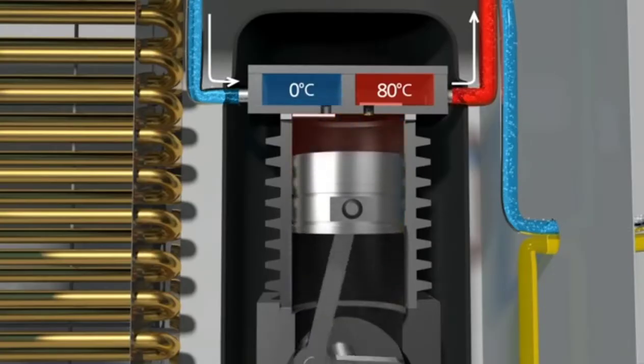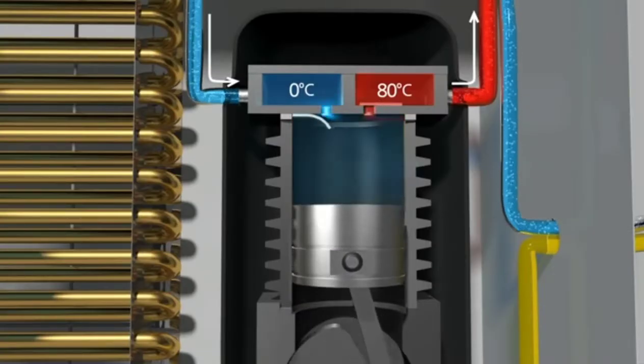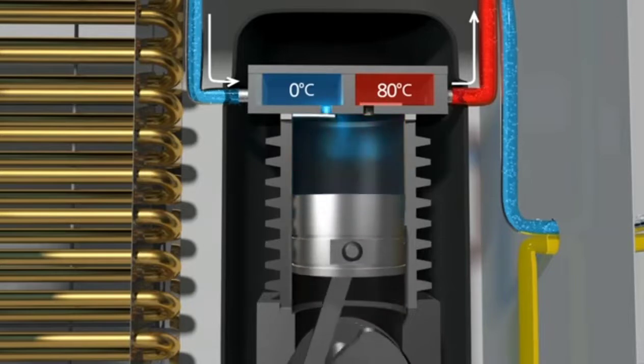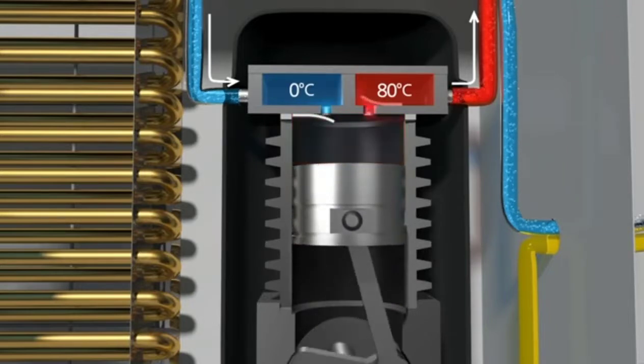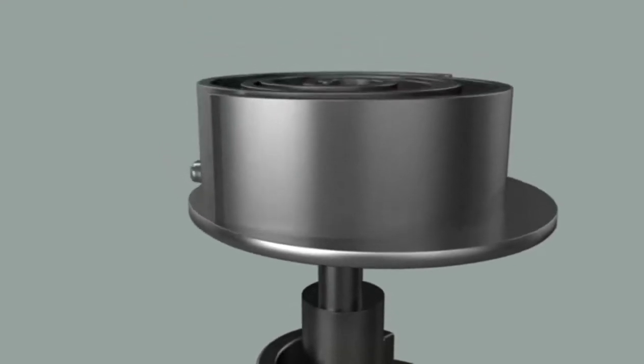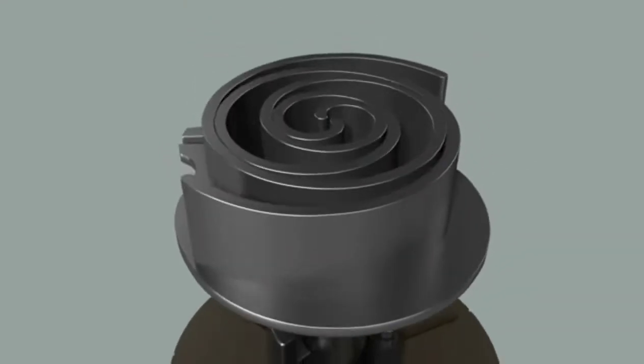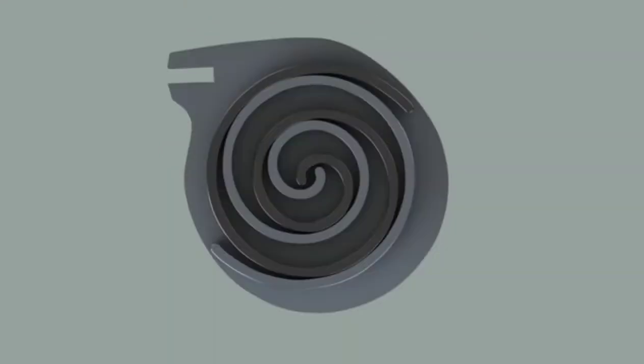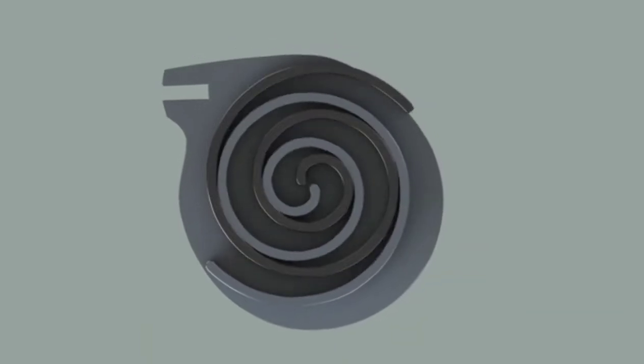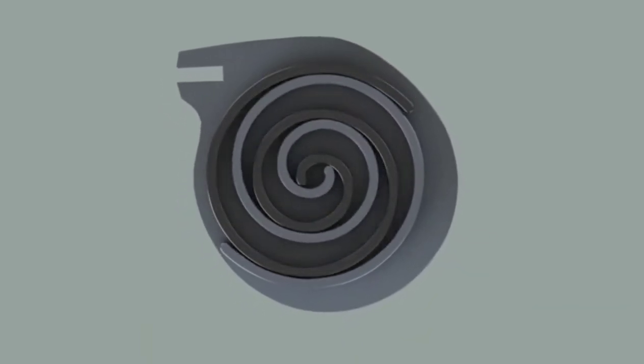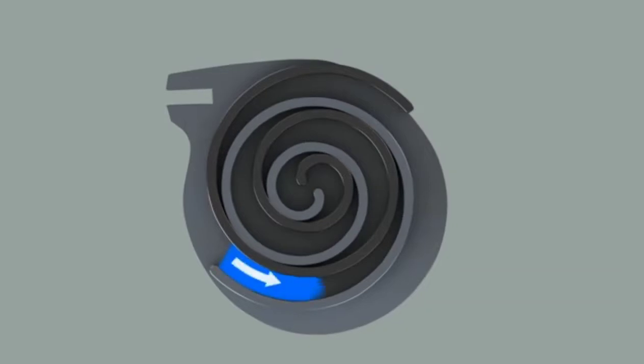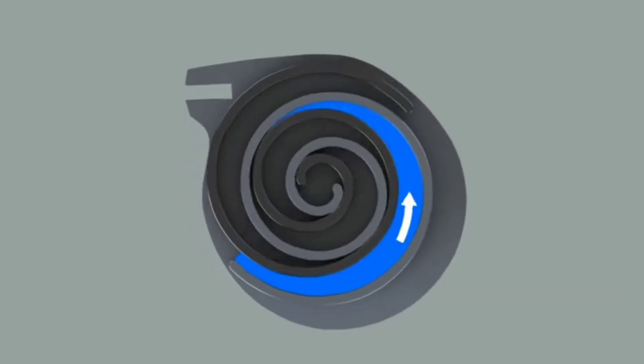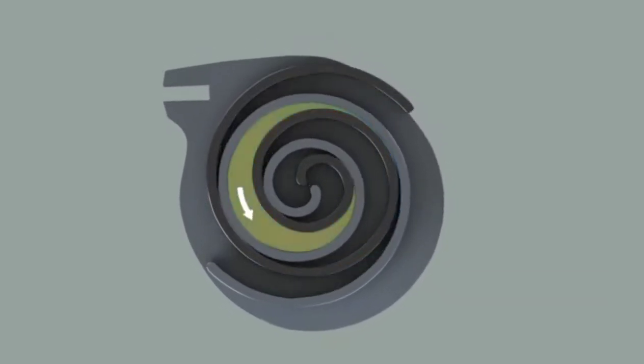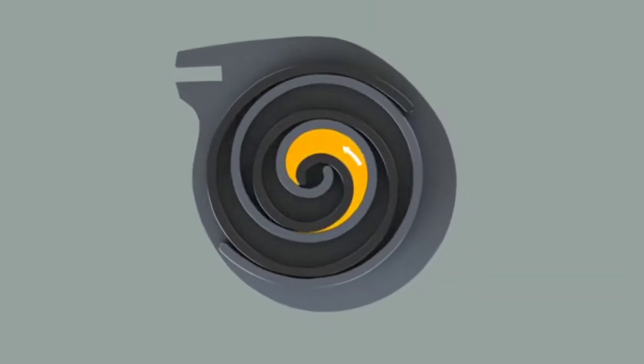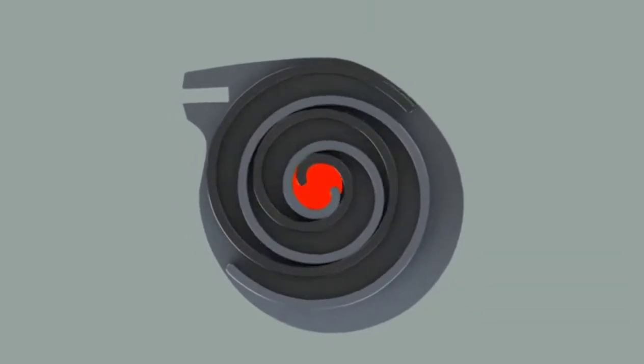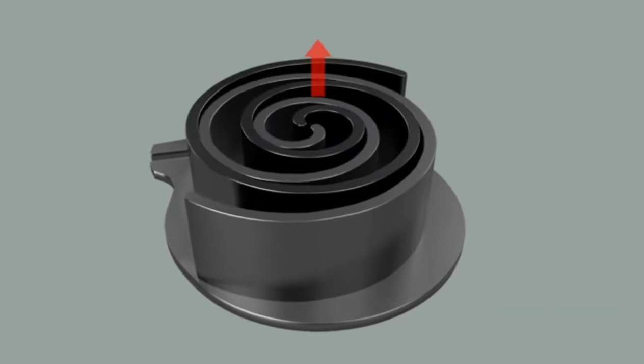Now, coming back to the case of an air conditioner. When gas with low pressure and temperature is pressed by a piston, its pressure rises, and so does its temperature. However, more air conditioners nowadays use a scroll type of compressor rather than piston type. In a scroll compressor, there are two scrolls of which one is fixed and the other rolls constantly. As more air coming through the entrance gets inside the scroll, space becomes crowded. As there is less space now, gas becomes more compressed and is discharged from the middle of the scroll in a compressed state.